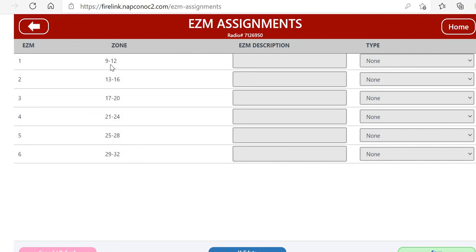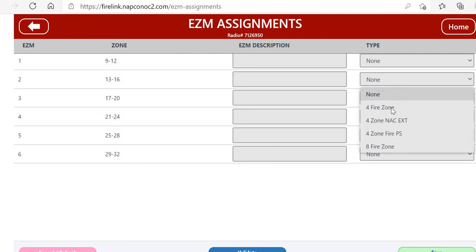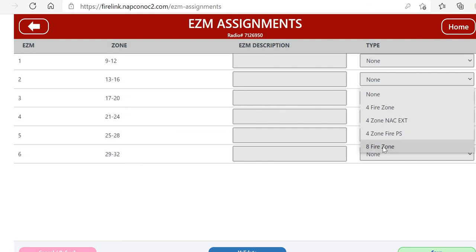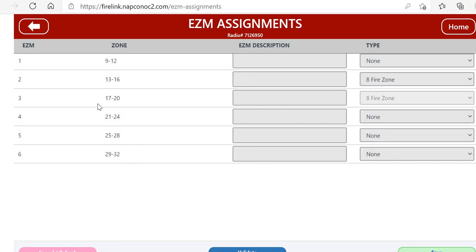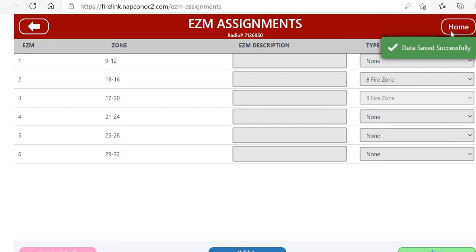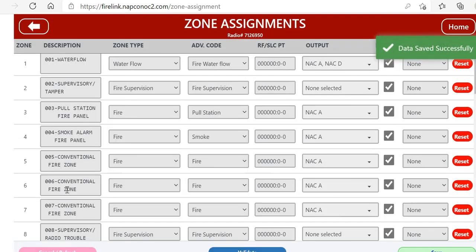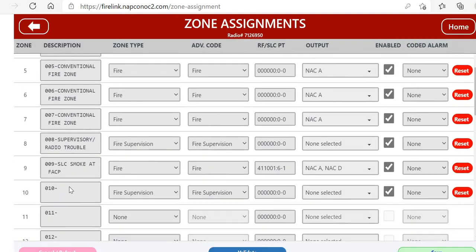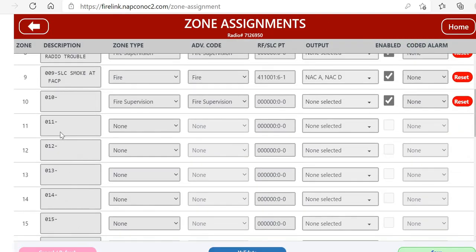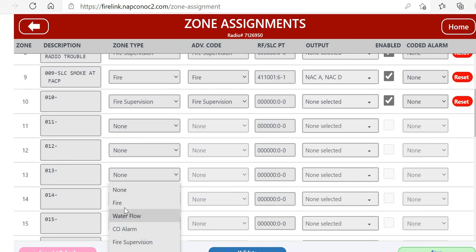We click on EZM Assignment. The thing to remember with EZMs - they come in banks of four, so they need to be in order. Because we already put some RF and SLC on zones 9 and 10, we're going to have to put our first EZM on addresses two and three because they take up two addresses on an eight-zone expander. So we would pick eight-zone fire and that would automatically populate EZMs two and three for zones 13 through 20.